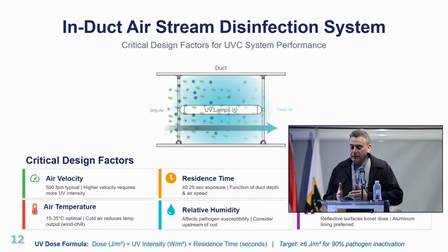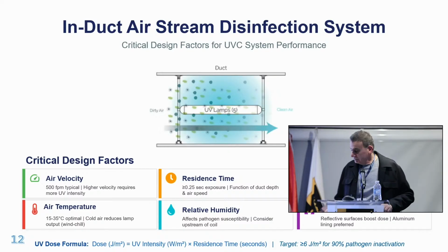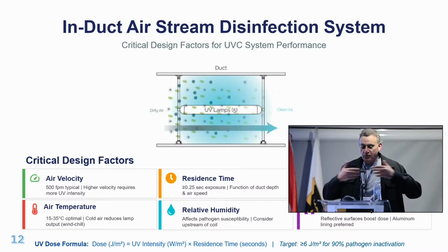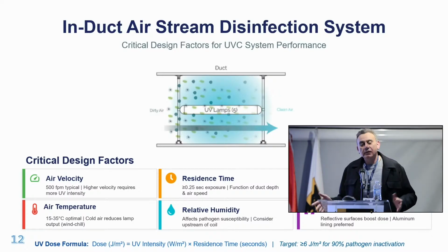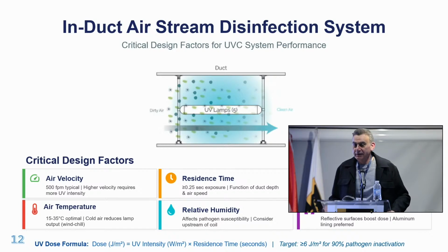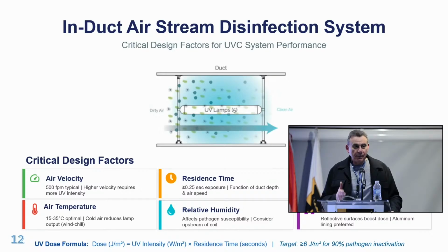Why? Because you need the air to be exposed to the lamp throughout the lamp's length. If you select an air handling unit and they give you a UV section with 4 or 5 lights perpendicular to the airflow, you're paying for nothing. It doesn't work. So the first option, the bulb needs to go parallel to the airflow.